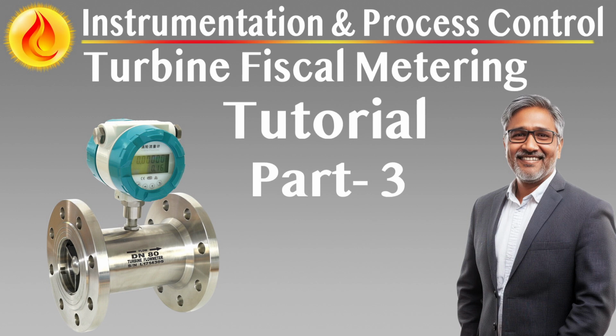Water cut measurement. Continuous monitoring of water content for net oil determination. Each fiscal metering station must include a water cut measurement system to quantify the water and oil content within the flowing stream. Typically, 2 water cut sensors are installed and operated in duty standby mode. The station microcomputer must automatically switch to the standby sensor in the event of a fault in the primary device.